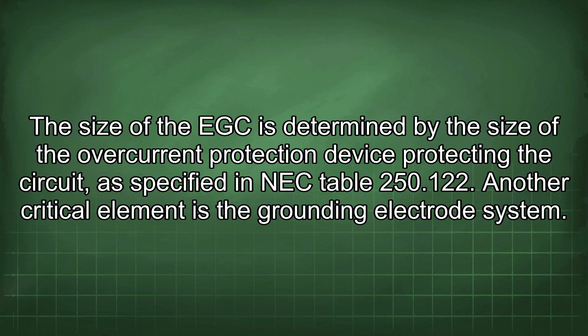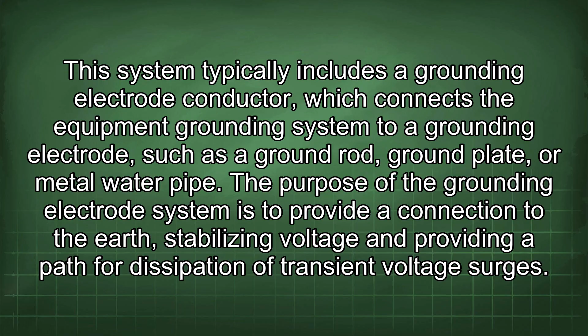Another critical element is the grounding electrode system. This system typically includes a grounding electrode conductor, which connects the equipment grounding system to a grounding electrode, such as a ground rod, ground plate, or metal water pipe. The purpose of the grounding electrode system is to provide a connection to the earth, stabilizing voltage and providing a path for dissipation of transient voltage surges.